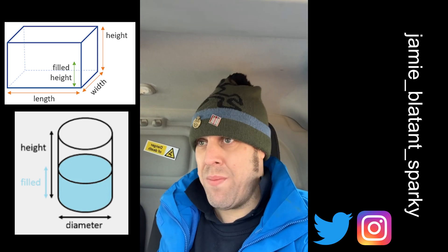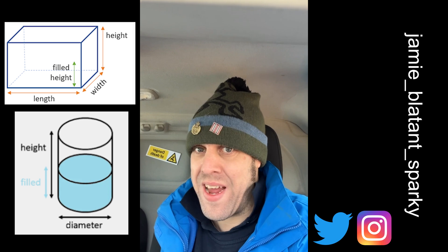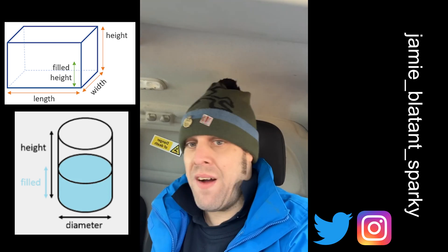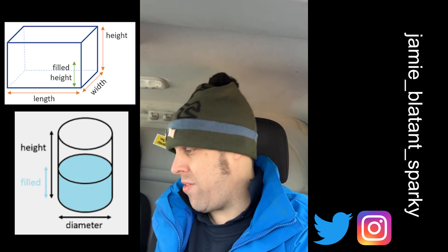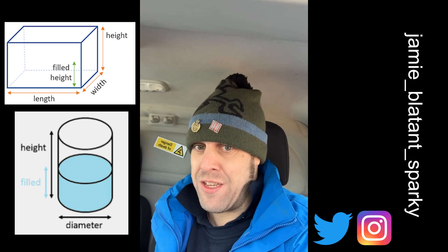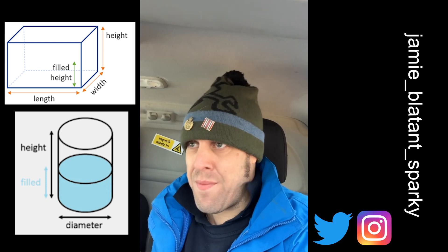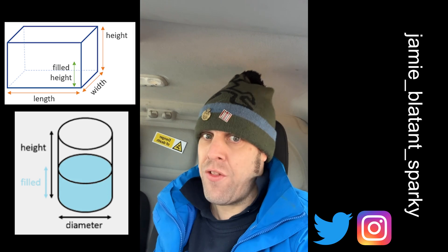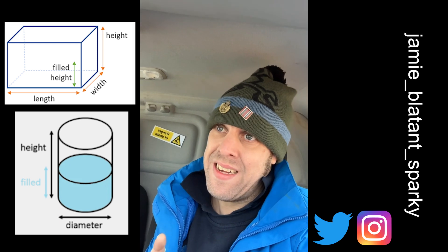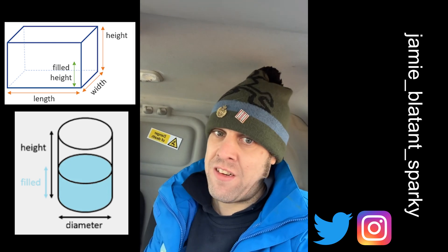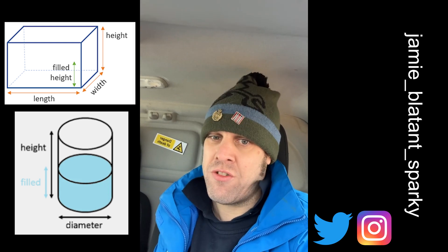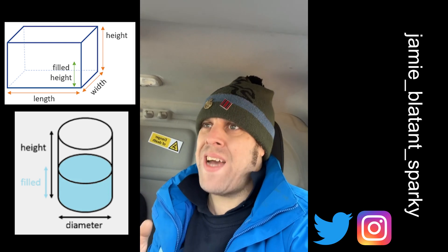The options you've got are weighing it — I'm not going to drag all the oil out to weigh it. So I've done some maths: I took the known height, width, and length of the tank, worked out the cubic metres, found out the manufacturer's data for the oil, done the maths, worked out the height that four thousand litres should be at, and I've dipped it with the tape measure — and it's right. So now I think we've been shortchanged.